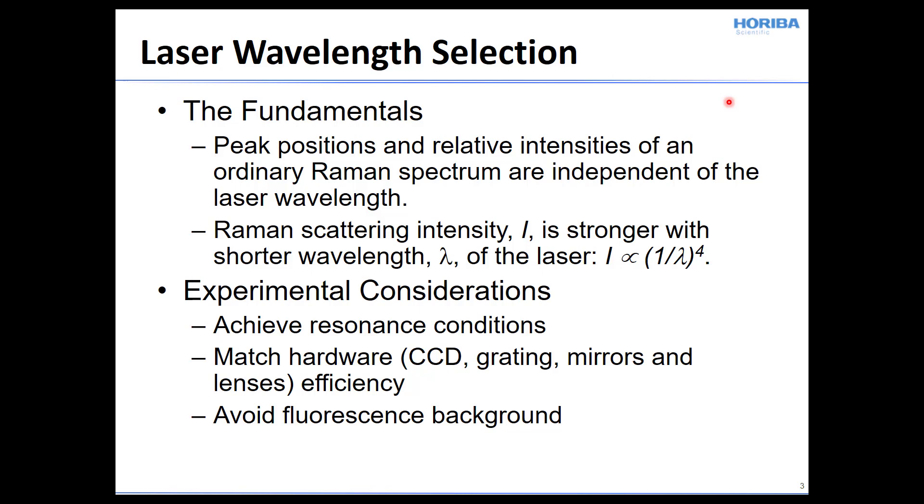In consideration of laser wavelength selection, let's start with the fundamentals. First is that the peak positions and relative intensities of an ordinary or normal Raman spectrum are independent of the laser wavelength. So whether you're using 532 nanometer excitation or 632.8 or 785 or 405 nanometers, the Raman spectrum that you generate should be the same as long as you're not in resonance, that is to say that there's no transition from the ground to the excited electronic state when using this laser excitation.